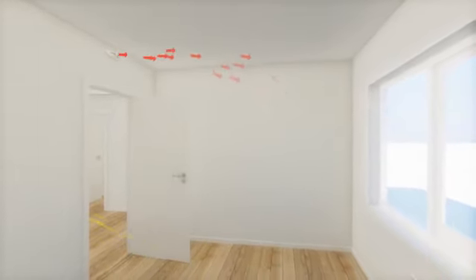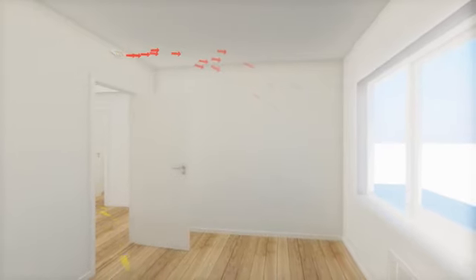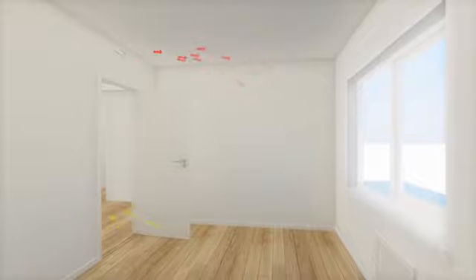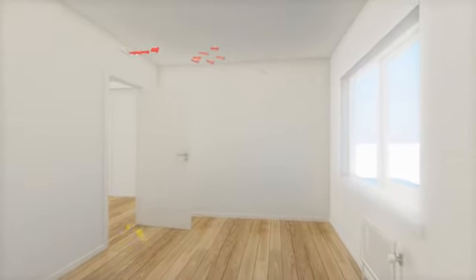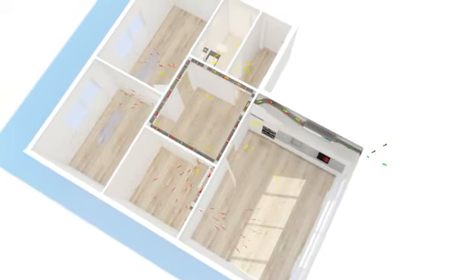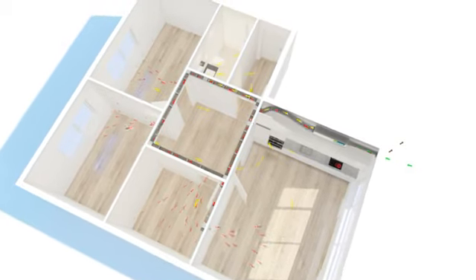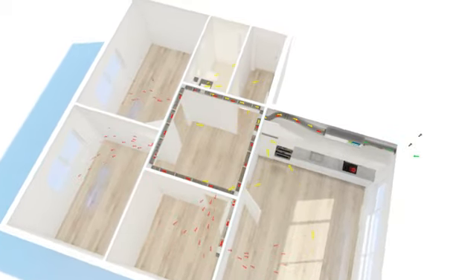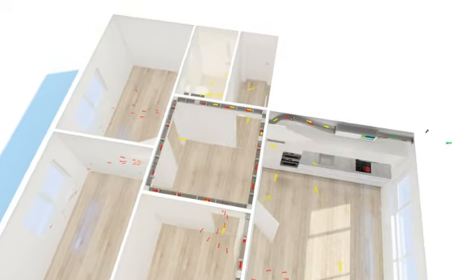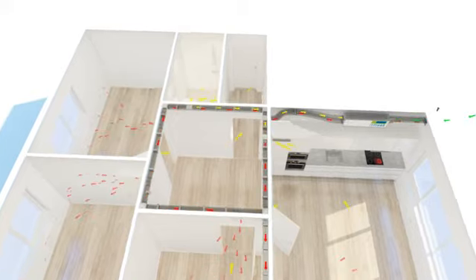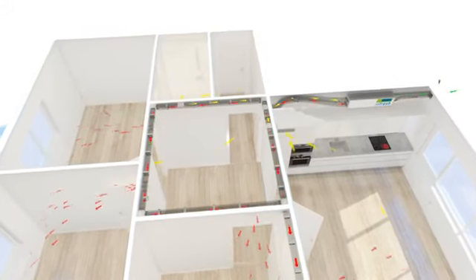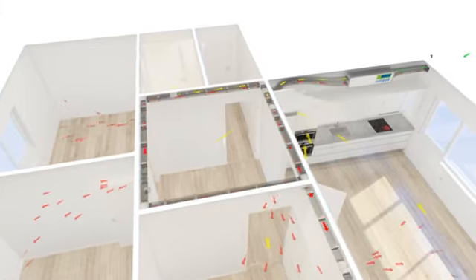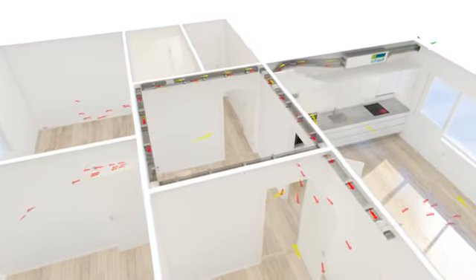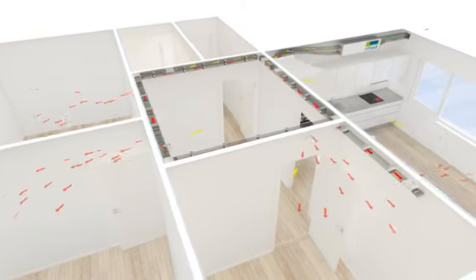Before the system is used for the first time, the Iquanda outlets and air handling unit are fine-tuned to deliver the precise amount of fresh air needed for each room in the flat without noise and without draft. Here you see the airflow in the flat when the refresh ventilation system is running. The fresh air is distributed in each room via the ceiling. The extractors in the kitchen and bathroom pull the air from the rooms through the hall and into the bathroom or kitchen. Here, it is expelled out through the extractor fans. This airflow creates an efficient and uniform air exchange in the flat and ensures maximum comfort and superb air quality.